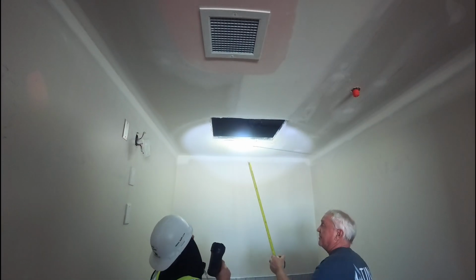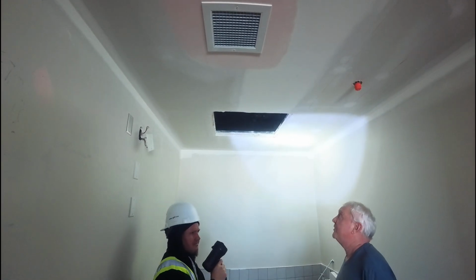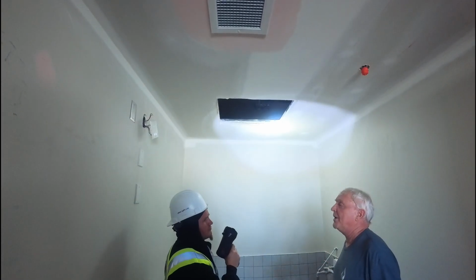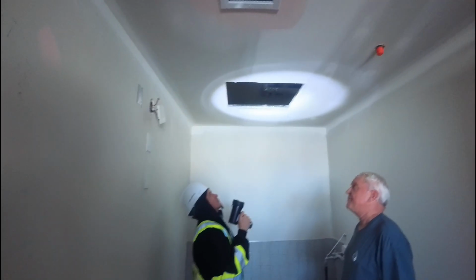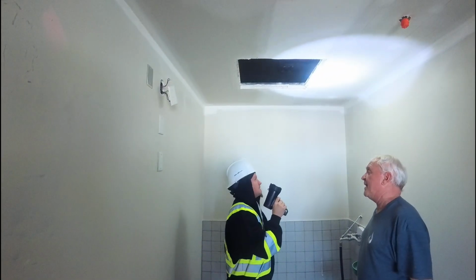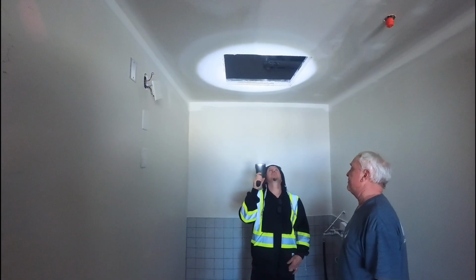Why is it double the drywall? That's 2 layers of 5/8 board, which is 1.5 hours fire rated. Why is it double here? Double it because it takes an hour and a half. That's a fire rated ceiling. It takes an hour and a half to burn through 2 layers of 5/8 board.